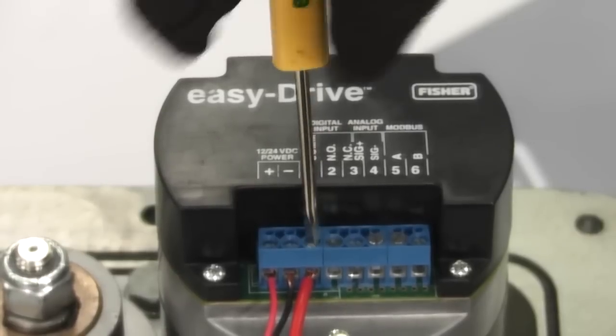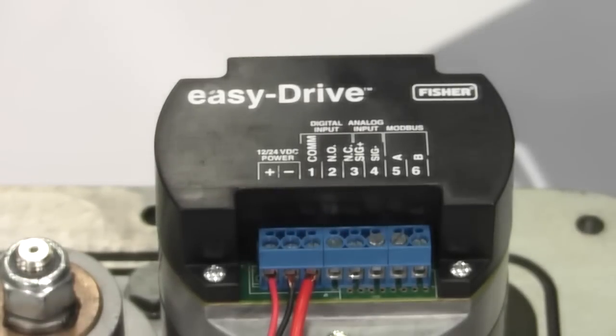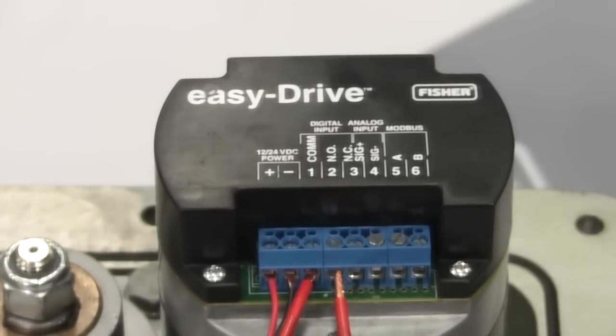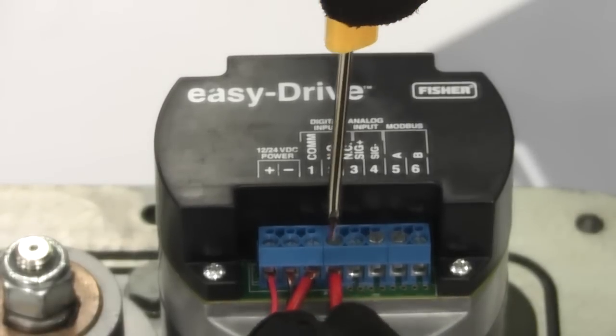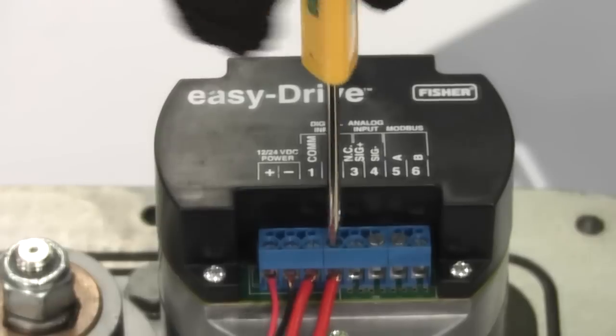When operating the valve in the single dry contact mode, the easy-Drive should be connected to the two switch wires at the common and normally open terminals. Terminals 1 and 2 respectively.